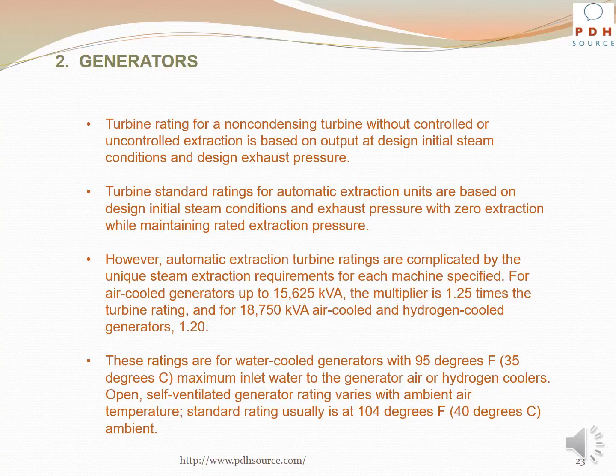For air-cooled generators up to 15,625 kVA, the multiplier is 1.25 times the turbine rating, and for 18,750 kVA air-cooled and hydrogen-cooled generators, 1.20. These ratings are for water-cooled generators with 95°F maximum inlet water to the generator air or hydrogen coolers. Open self-ventilated generator rating varies with ambient air temperature. Standard rating usually is at 104°F ambient.